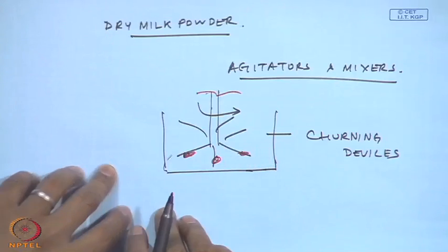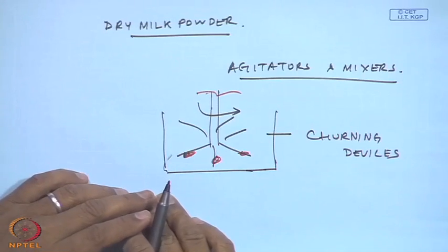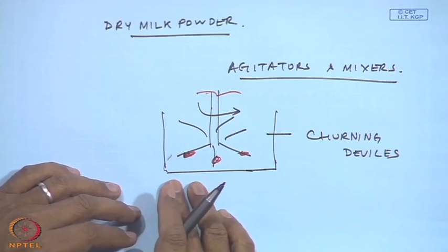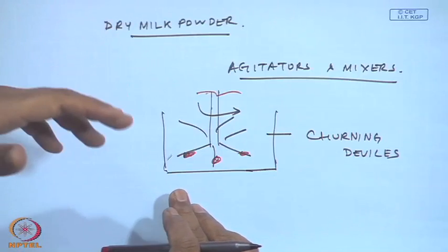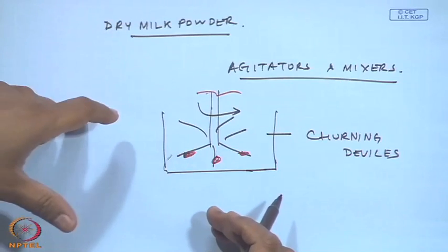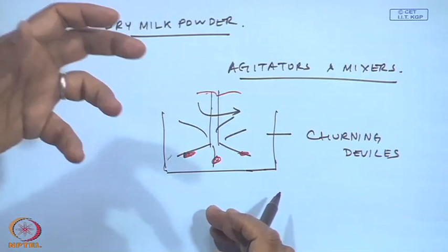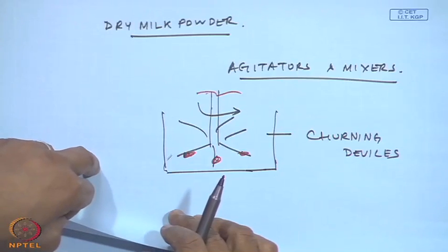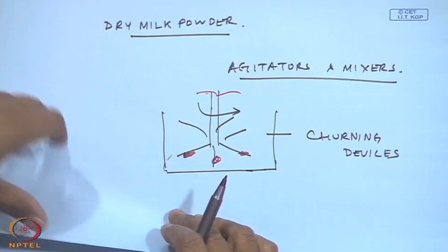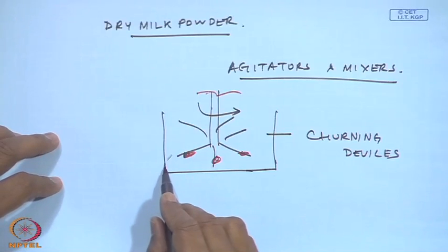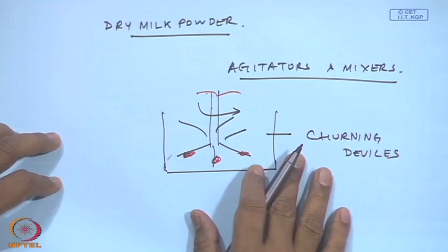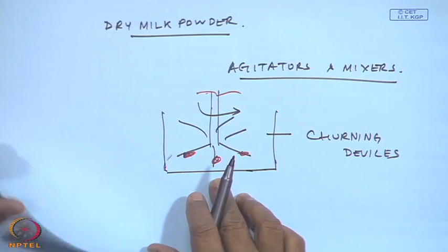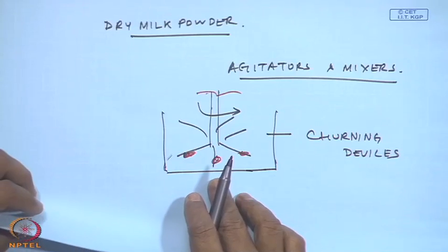So, periodically in many of these plants, be it the FD fan in a power plant, be it an agitator in a food processing plant, in regular maintenance they scrape off the deposits, and there are alarm levels also. If they suddenly see that the weight increases, etcetera, they know that something is getting deposited. You are talking about an iron ore sintering plant, okay. A lot of things happen, a lot of places where things can get stuck, they will create an unbalance and then things will break off. Okay. So, the sources of unbalance are manufacturing defects, installation issues, maintenance issues and so on.